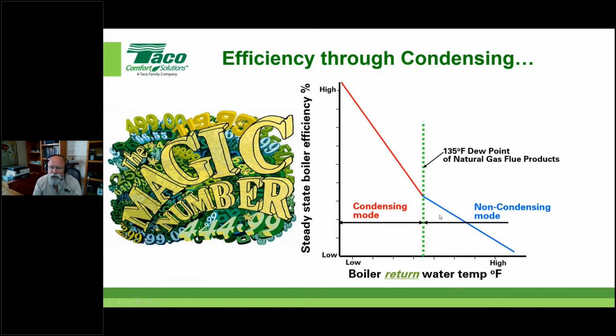If you look at this chart that comes to us, I've seen this from ASHRAE, and almost every boiler manufacturer out there that sells condensing equipment uses something that looks just like this or similar to this to some extent. But you notice there's this magic spot in which the pitch of this curve changes quite a bit, right? And this spot here, it's pointing out that it's 135-degree dew point for natural gas flue products. But that's not the number we're looking for. That just tells you the science is happening back inside the combustion chamber and stuff. What we're looking for is a fluid temperature that's low enough so that the surface temperature can actually see condensation.